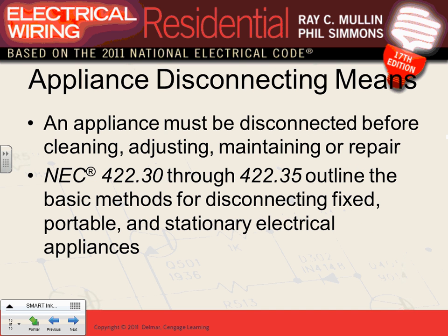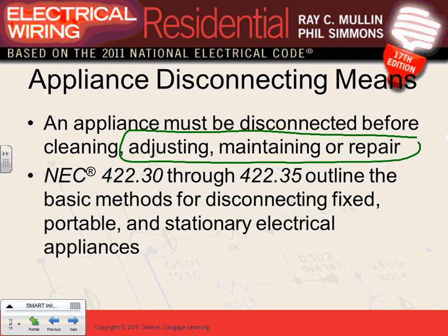Appliances need a disconnect, guys. Must be disconnected before cleaning. All these appliances have to have a disconnect. Why do we have a disconnect? And we keep talking about the disconnect, guys. Because of maintenance, repair, adjustment. We're just tired of people cutting their fingers when they're working on these fans because the fans kicked in. So the thermostat typically has an off position. You put it in the off position, you go remove that cable, or you can have a snap switch right next to it.